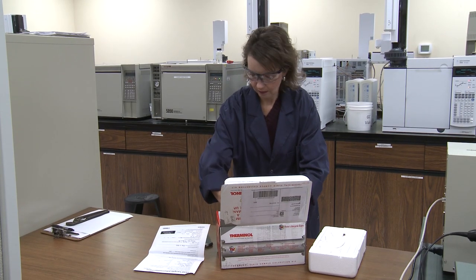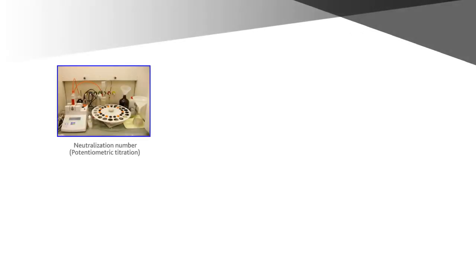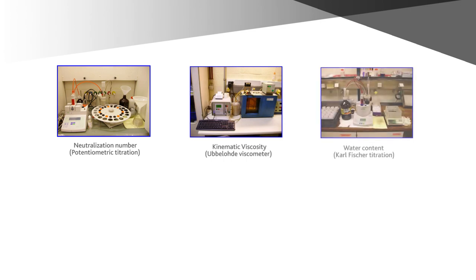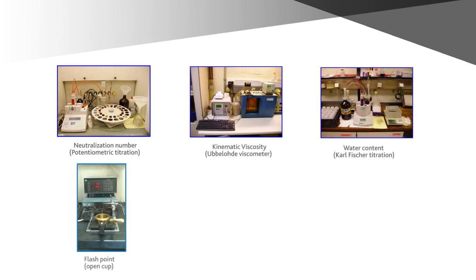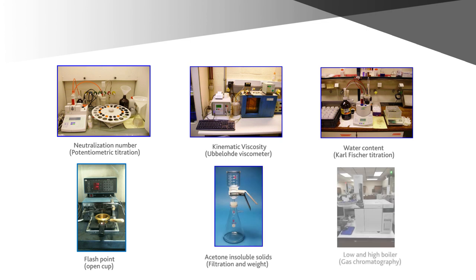Check with your fluid supplier's lab to verify the tests they will perform and the reporting you will receive. A qualified lab technician should analyze your sample for several important performance factors, which may include neutralization number, kinematic viscosity, moisture content, flash point, acetone insoluble solids, and gas chromatography. Additional special analysis may be available upon request.